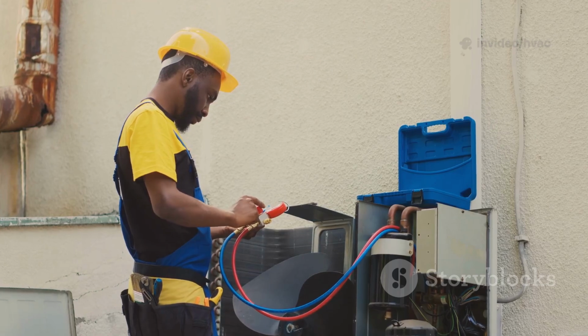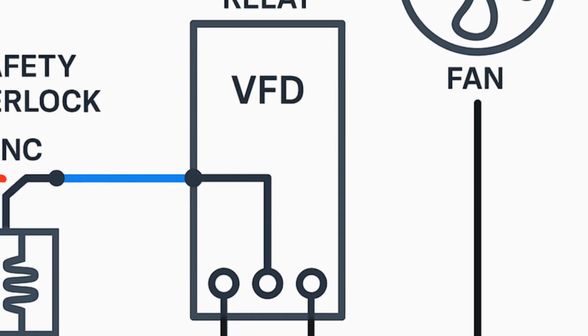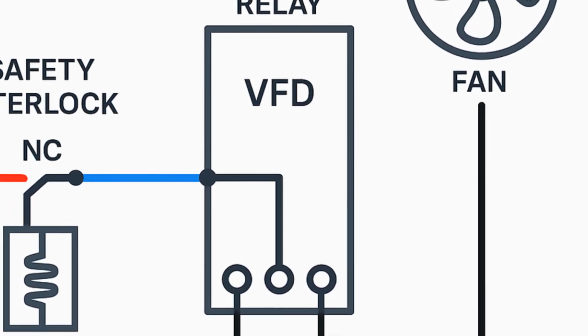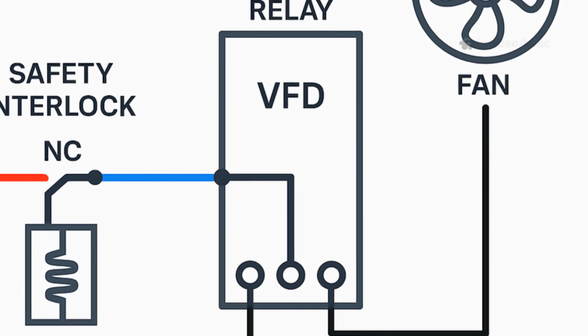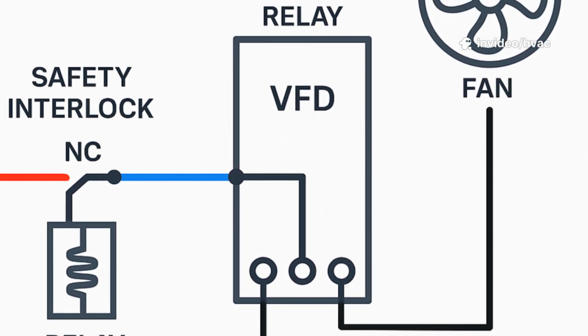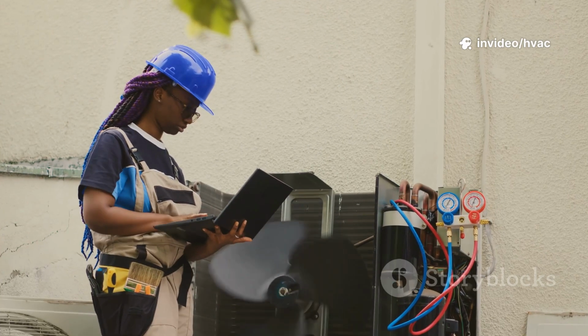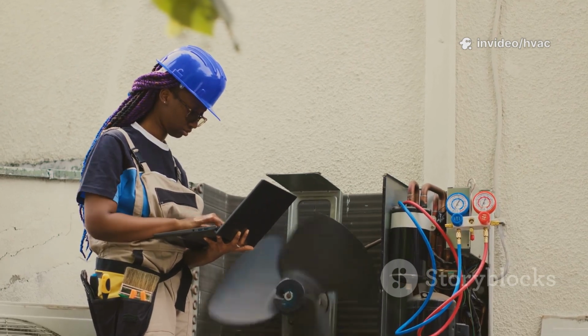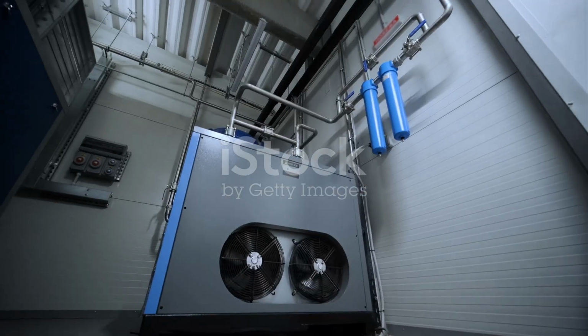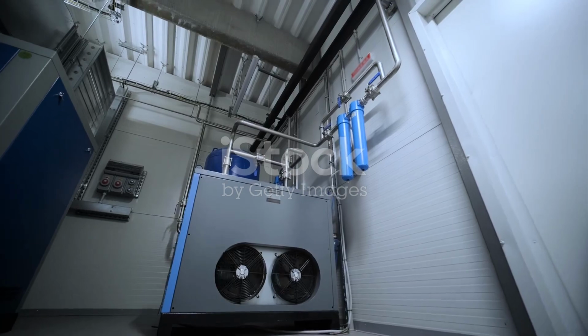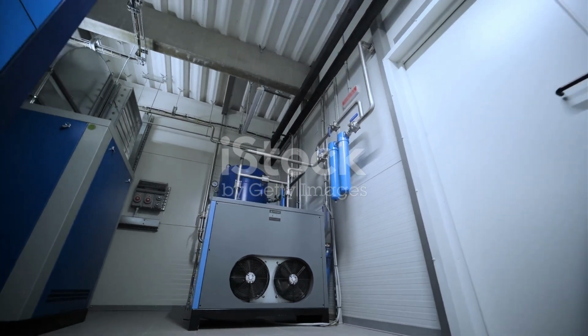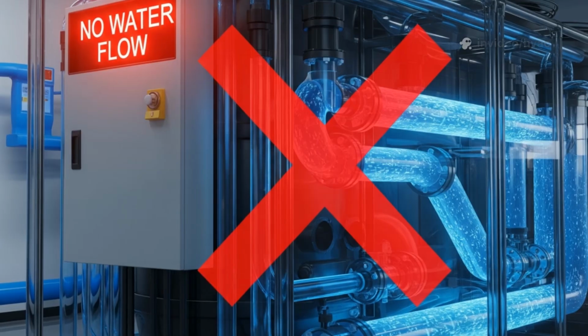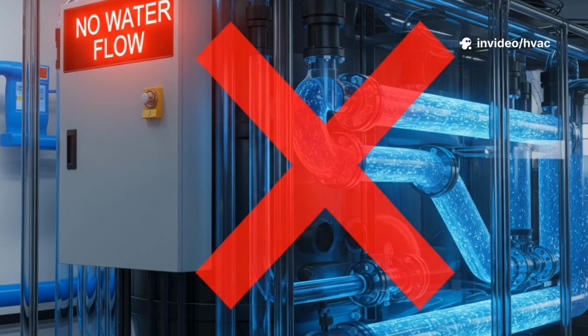Let's see interlocks in real HVAC systems. In air handlers, the supply fan must be proven on before heating or cooling elements activate, using pressure switches or current relays. If the fan fails, heating and cooling are disabled, preventing damage. Chillers are interlocked with both chilled and condenser water pumps. Both must prove flow before the chiller starts. If a pump fails, the chiller shuts down instantly.